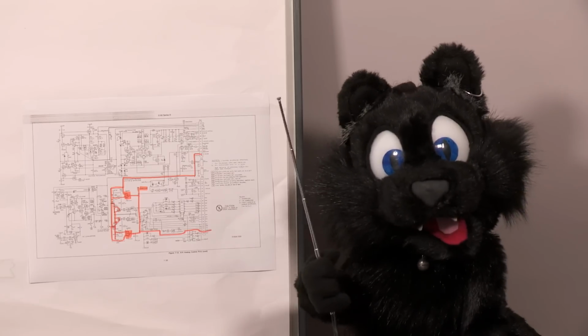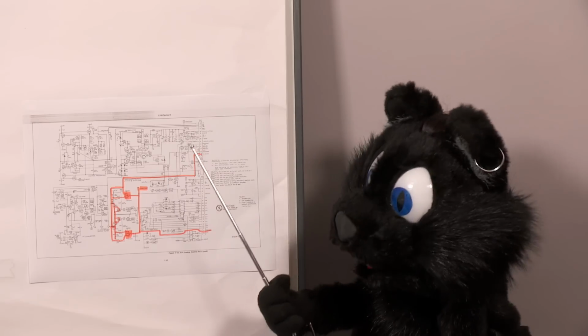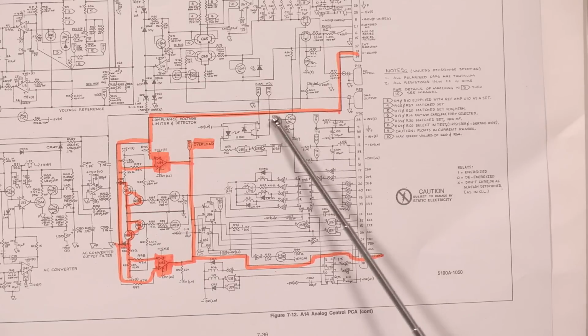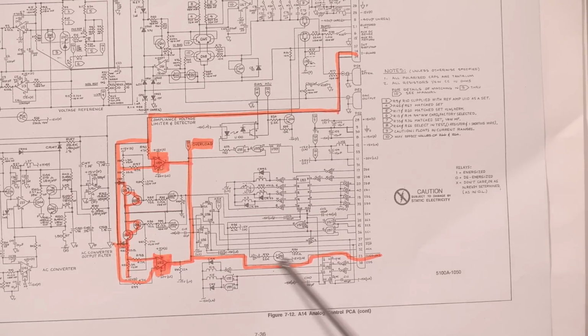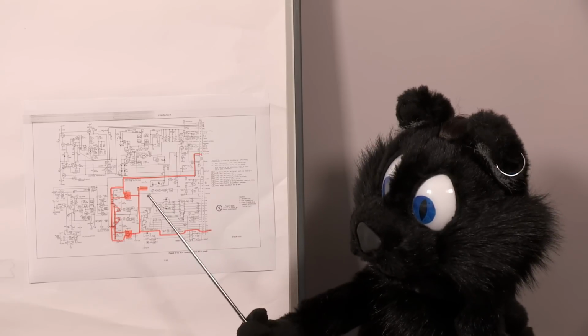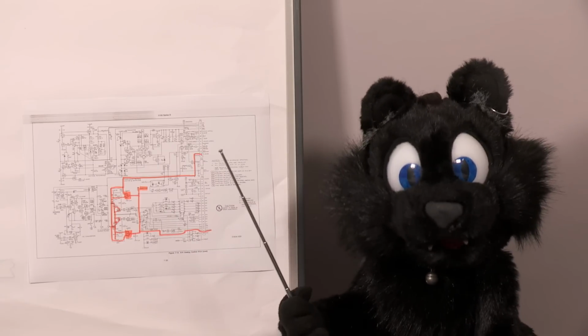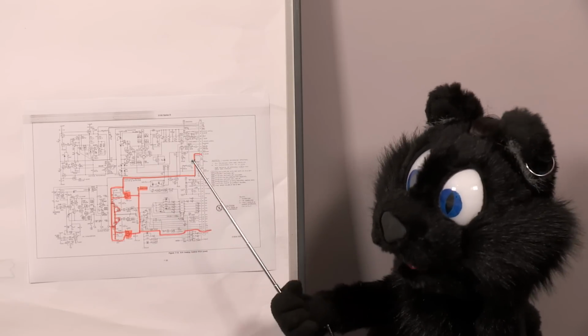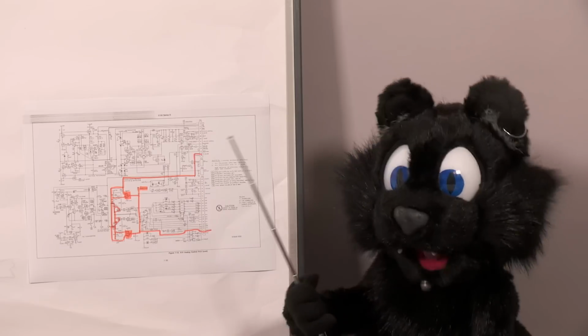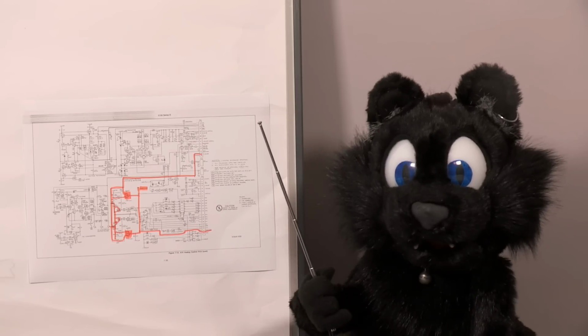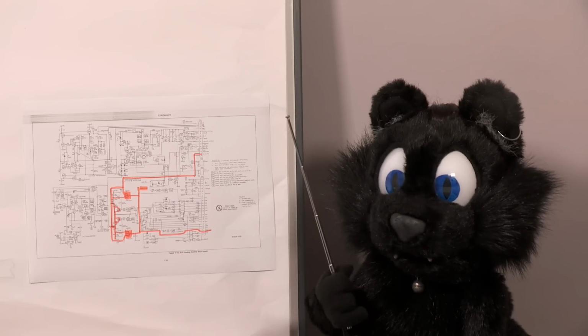Time for some troubleshooting. This here is the analog control board and the only place that drives the overload signal for the controller. I spent hours following the signals all over to see what causes the condition, which should only relate to current, not voltage delivery.